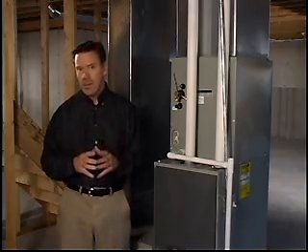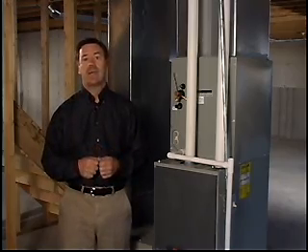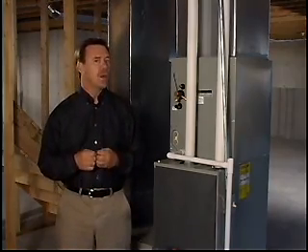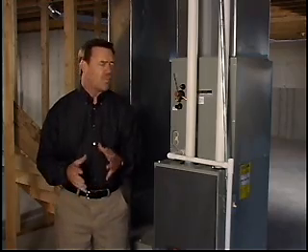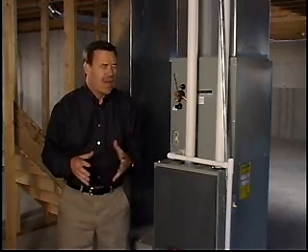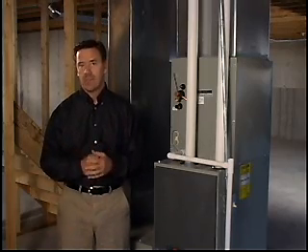Another important part of HVAC systems is their design. Oftentimes we tend to oversize HVAC systems, particularly air conditioning systems. And when we oversize them, they never really run long enough to dehumidify the air. They cool the air down quickly, but don't run long enough to take the moisture out of the air, so the house can feel kind of cold but clammy. So it's important that we size the system appropriately.